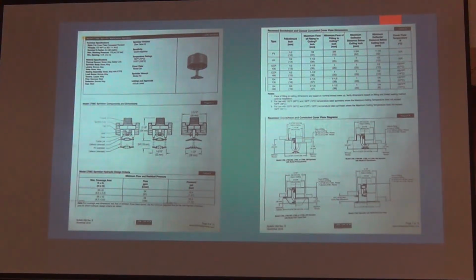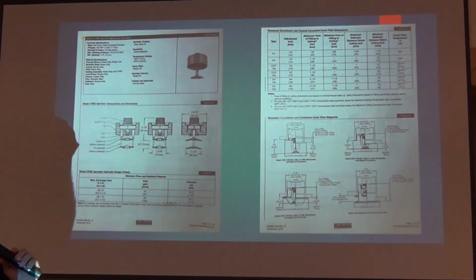That solder lets go. That little spring you've seen just drops, caught in the carpet. This little spring right here will assist the cover in dropping off. It will then expose the sprinkler head below it or above it and expose it to the heating element here, which you've seen in the last slide. No matter what Hollywood tries to tell you, smoke does not activate sprinkler heads, unless the smoke is 165 degrees or hotter, then it's called a fire.